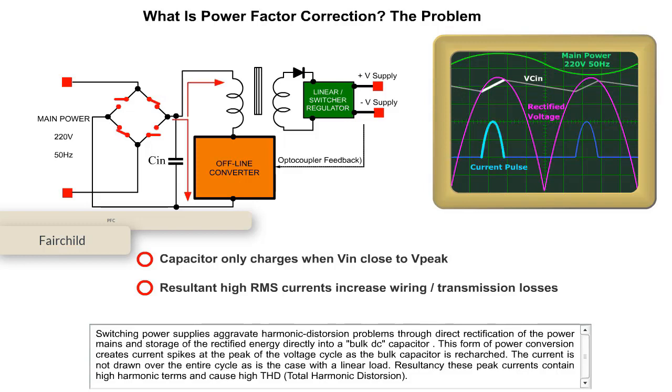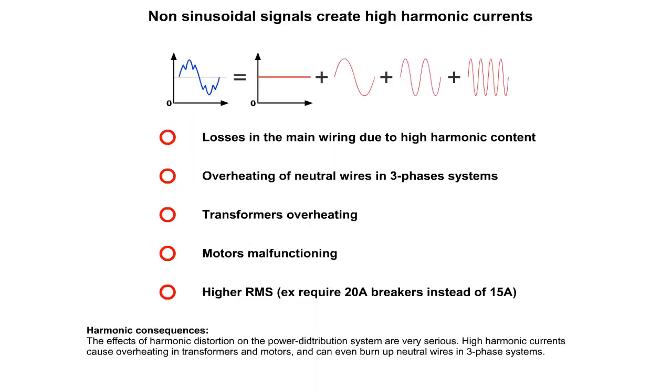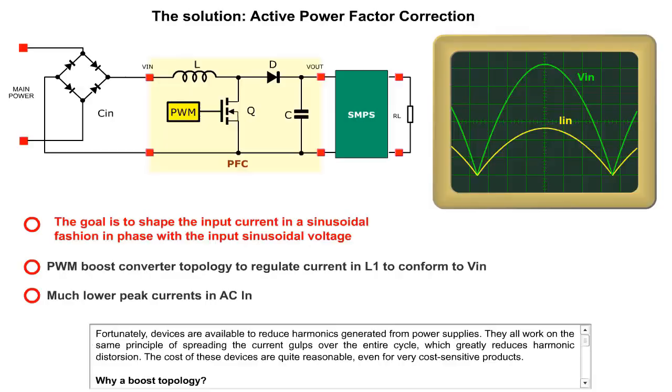This entails bringing the power factor angle closer to 0 degrees to reduce the phase difference between voltage and current, so that the apparent power approaches the effective power. At the same time, harmonic currents are suppressed. Suppression of harmonics is prescribed by class in the International Standard IEC 61000, which stipulates the maximum allowable harmonic currents, and PFC is essentially required for relevant electronic devices.